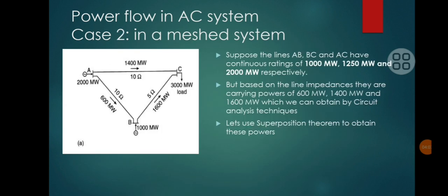Case 2 of a power system is a meshed system. A basic network is shown here having three buses and three transmission lines. A, B, C are the buses. AB, BC and AC are the transmission lines having impedances of 10 ohms, 5 ohms and 10 ohms respectively. Also, the maximum ratings of these lines are AB 1000 megawatts, BC 1250 megawatts and AC 2000 megawatts. But based on the line impedances, they are carrying powers of 600 megawatts, 1400 megawatts and 1600 megawatts.